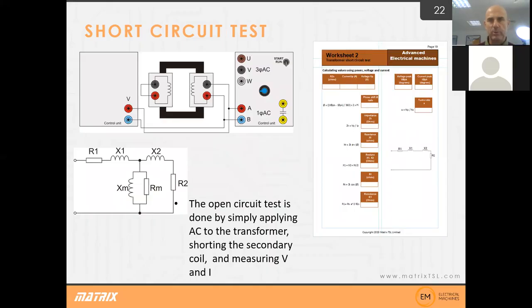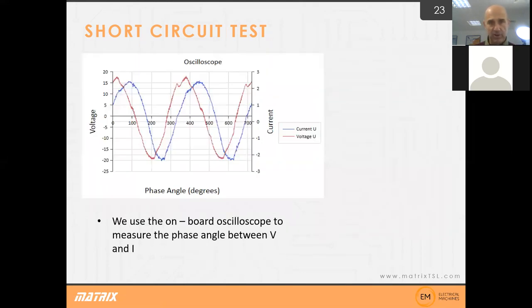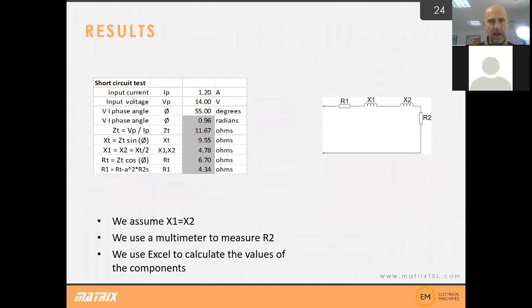The second part of the problem is the short circuit test. It's very similar, the only difference is we short circuit the secondary side. The sequence of calculations is almost identical, and that allows us to come up with a set of values. We had 80 ohms and about 60 ohms for the magnetizing components, and the rest of the components are all under 10 ohms. So our original assumption about the relative values of these things is quite true.